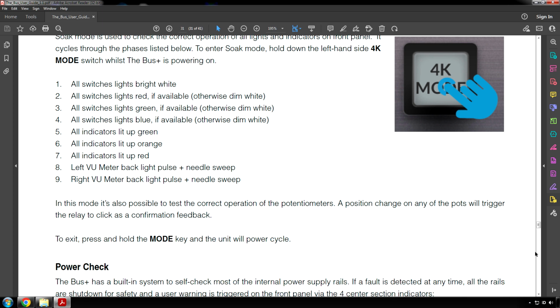In this mode, it's also possible to test the correct operation of the potentiometers. A position change on any of the pots will trigger the relay to click as a confirmation feedback. To exit, press and hold the mode key and the unit will power cycle.